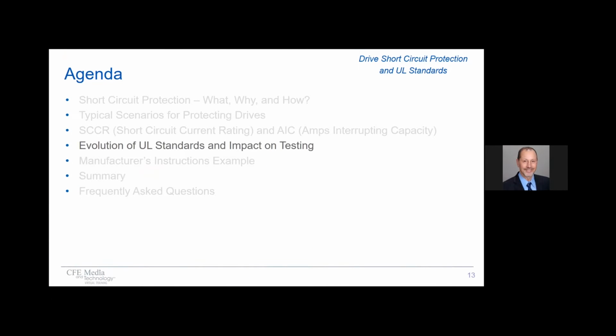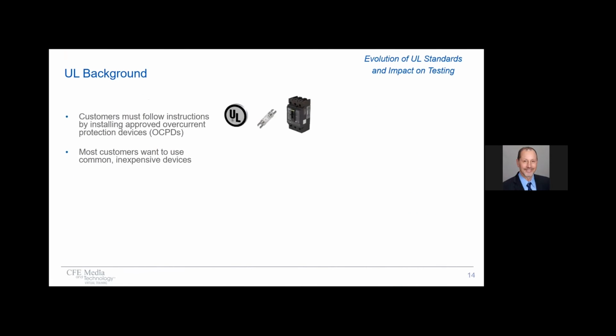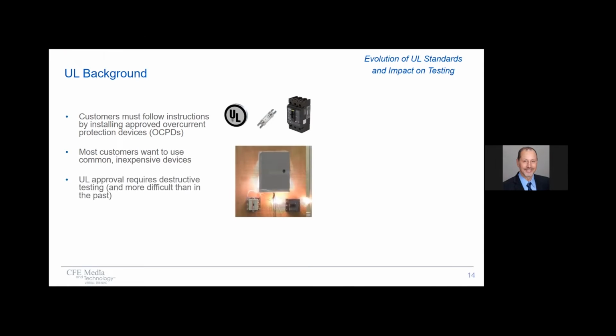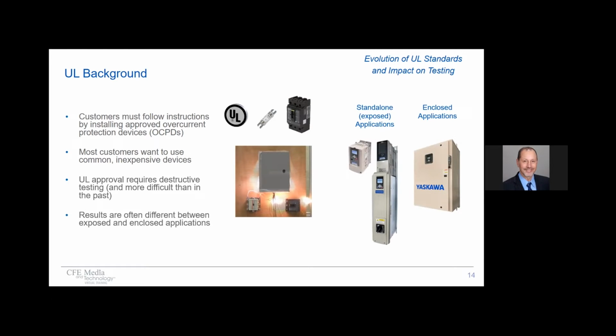Now with that foundation, we're more prepared to look at how UL standards and testing have evolved relative to drive protection. As most of us know, system designers and installers must follow instructions by installing approved protective devices. They also obviously want to use common inexpensive devices. What you may not know is that UL approval actually requires destructive testing, and it has become much more difficult than in the past. Also, results are often different between what we would call exposed applications, such as a drive mounted directly out in the open, and enclosed applications, where a drive is mounted inside of a supplementary enclosure.